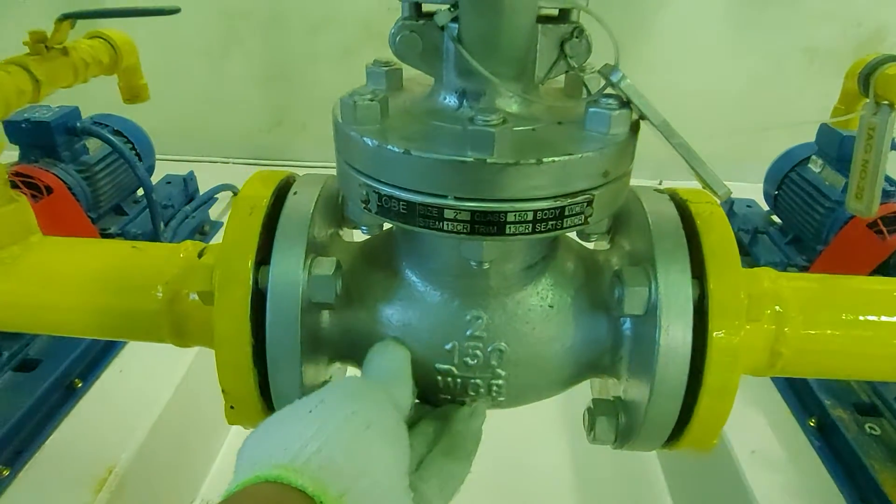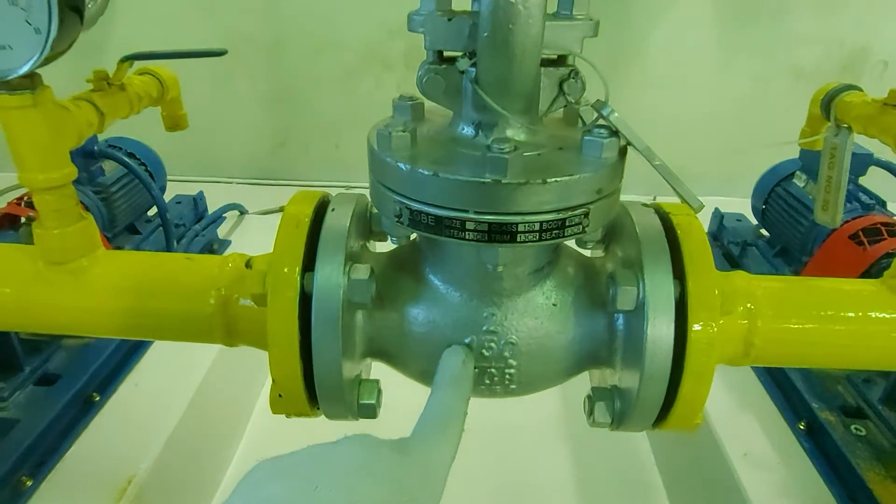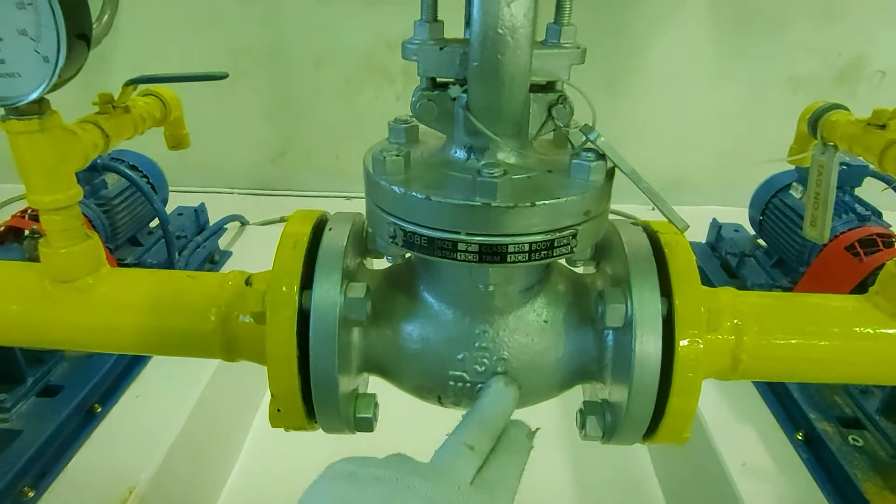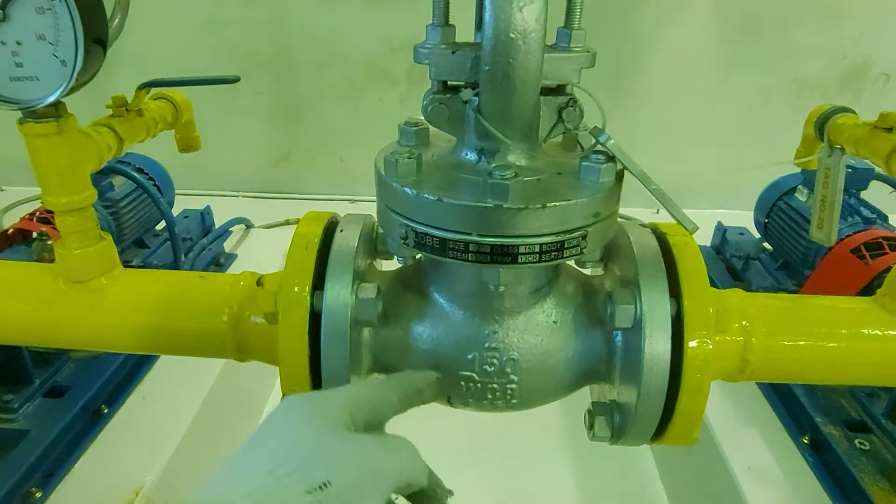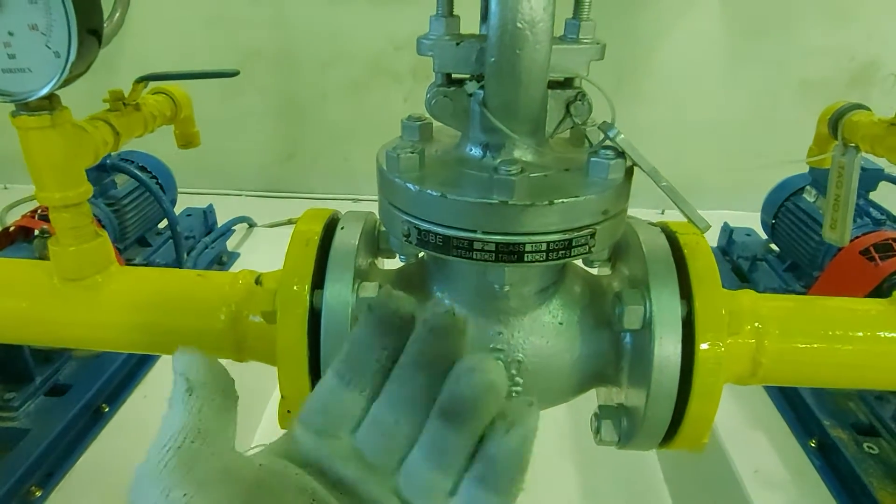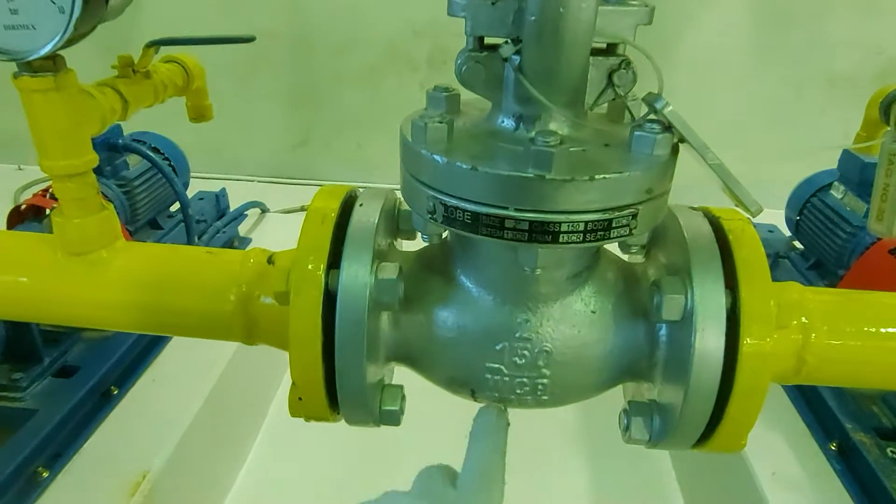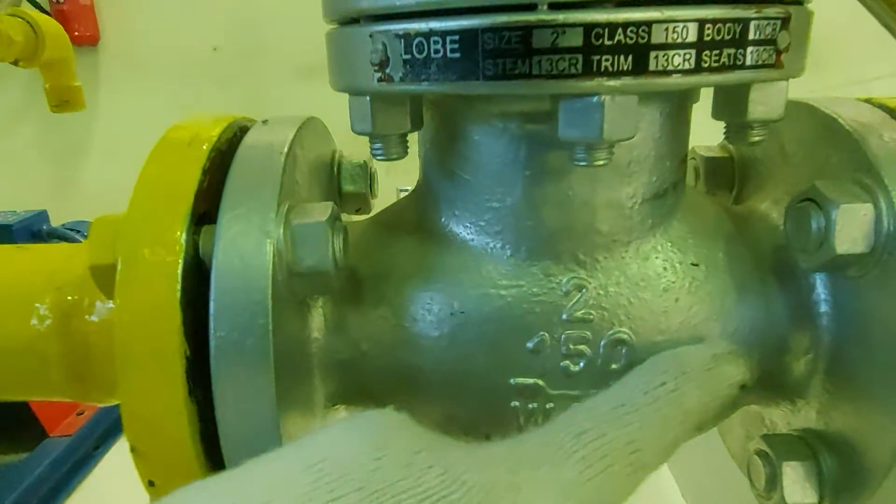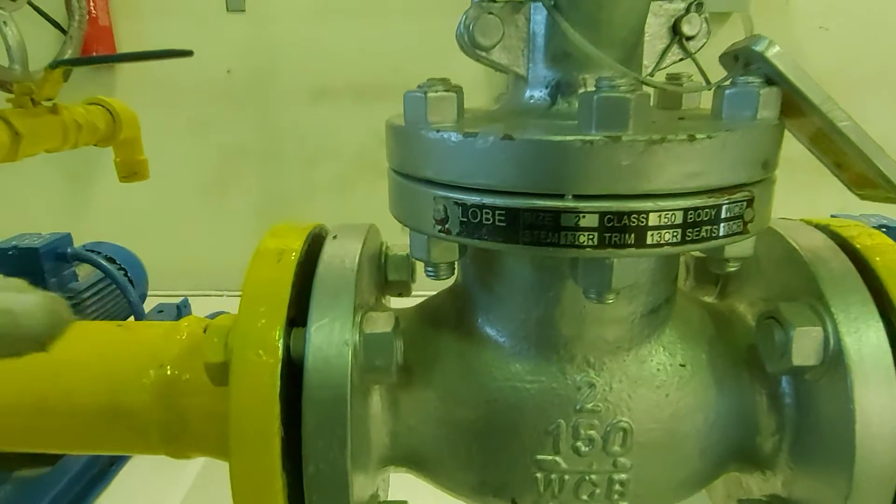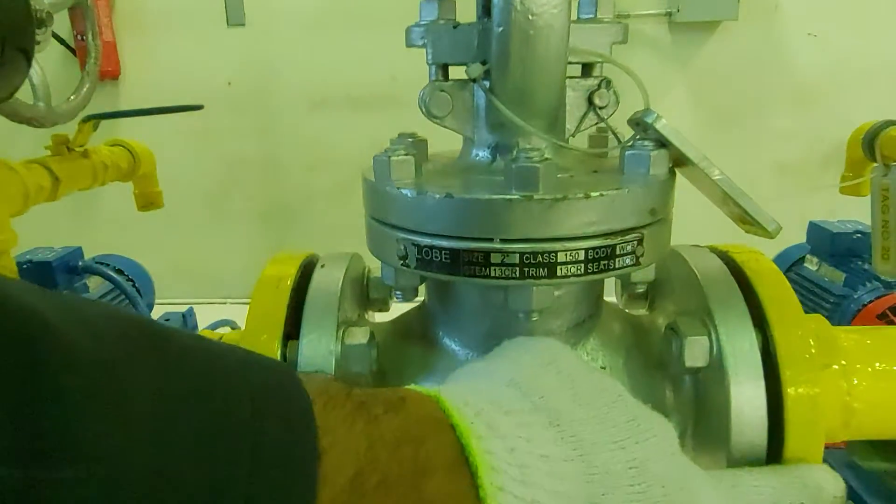And you will have another thing - gate valve and globe valve. So globe valve is single direction. You cannot use it in two ways. You cannot flip the valve and use it in opposite direction because there is an arrow. You see, it works in only this direction. So inlet should be here, outlet here, cannot be changed, cannot be flipped.